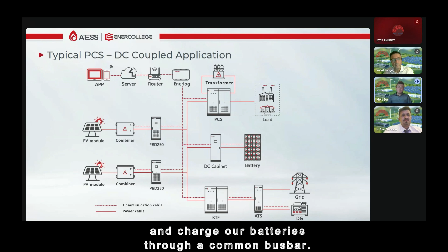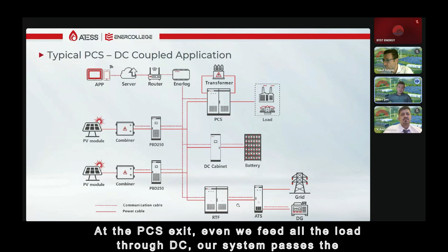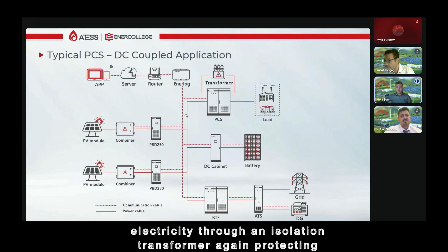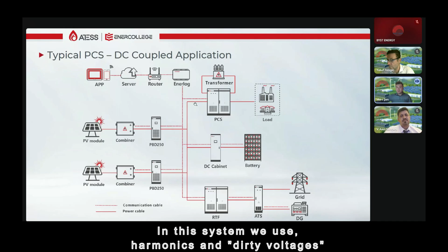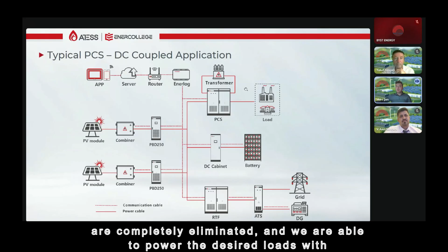The reason for this is as follows. Thanks to DC coupling, we convert all the incoming electricity and charge our batteries through a common bus bar. In addition, we feed our PCS. At the PCS exit, we even feed all the load through DC. Our system passes the electricity through an isolation transformer, again protecting our factory from peak loads. In this system we use, harmonics and dirty voltages are completely eliminated, and we are able to power the desired loads with 100% clean and reliable electricity.